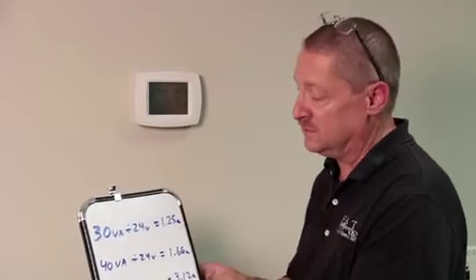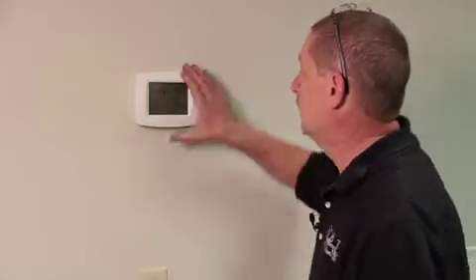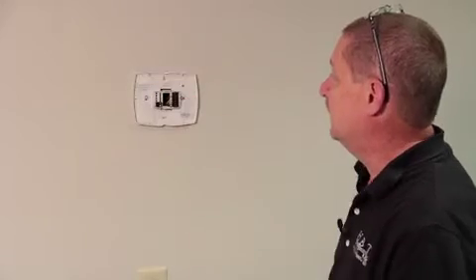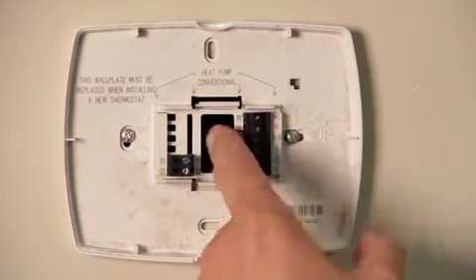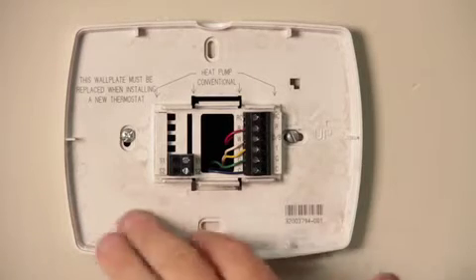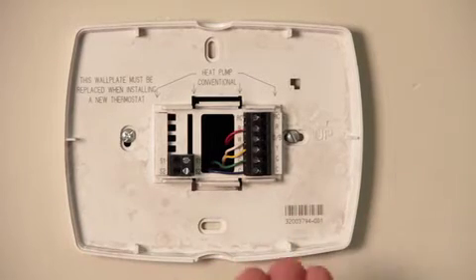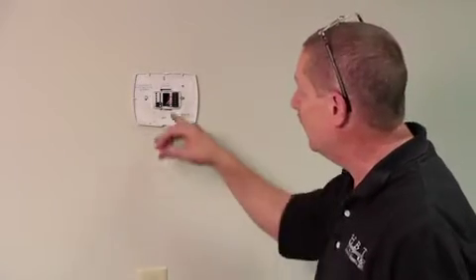As we pull off the thermostat, notice this one has an issue right away - I've got a hole behind it. That's where drafts... you can see the dirt buildup. Anytime you're seeing dirt buildup behind the thermostat, that means it's breathing - there's air moving in and out. We want to plug that hole so it doesn't affect the cycle rate.